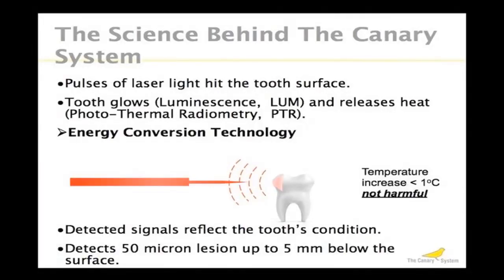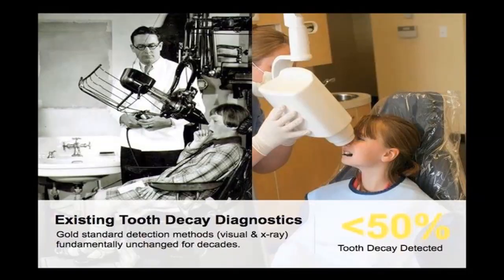The Canary uses two components to its technology: luminescence and photothermal radiometry. This is different than any other product out in the marketplace. It's a laser-based product that scans into the tooth. The laser is actually modulated so that the heat penetrates into the tooth. We have the ability to read 5 millimeters into the tooth structure. Between the luminescence and the photothermal radiometry, we then get a number to determine the health of the tooth. Most products on the market are measuring bacteria on the tooth surface. We are actually going into the tooth structure and measuring what the crystal structures are like.